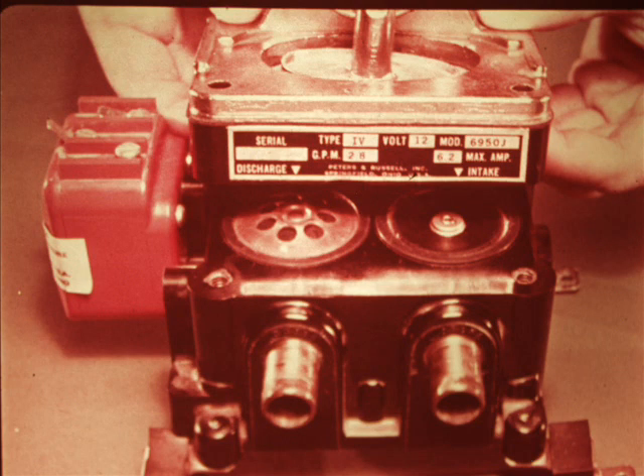When you replace the assemblies, be sure that the rubber valve with the small hole is up on the intake and the rubber valve without the small hole is down on the discharge. Take care that you do not use a valve with a small hole in the rubber discharge side of the pump. Also, because the diameter of the hole is critical to the pump's proper operation, it must not be enlarged.